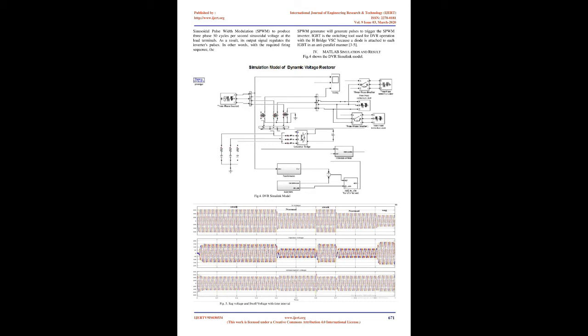Consequently, DVR is a static device connected in series with the system, used for compensating voltage sag and swell. For compensating voltage, a number of devices are used, such as UPQC, SVC, D-STATCOM etc. But due to their large size and critical operation, these devices are only sometimes used. DVR is the cheapest in cost and simple in operation, so it is widely used in the system.